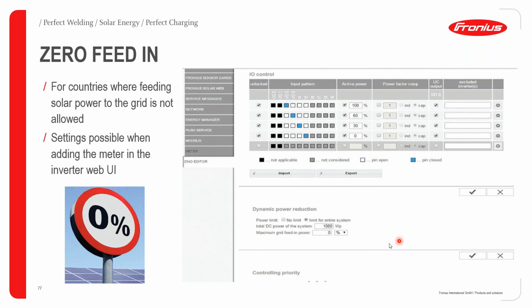So also, one very important use of the Fronius smart meter is for zero feed-in control, because in most countries where feeding of solar power is not allowed to the grid, you need the smart meter to be able to achieve this setting or this limitation.